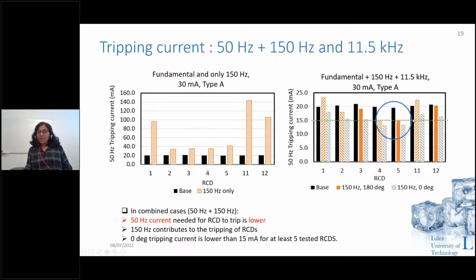the second one where we have 30 milliampere RCDs, 150 hertz and 11.5 kilohertz, and these are all type A RCDs. And in type A RCDs, particularly, we saw that for these two RCDs, let's say for 150 hertz 0 degrees, they were tripping at lower than 15 milliampere. On the left, this one is where you have 150 hertz and fundamental comparison. So we just try to trip with the 150 hertz component, and all the RCDs, of course, tripped, and they have tripped with much higher current because this is a pure tone 150 hertz component.